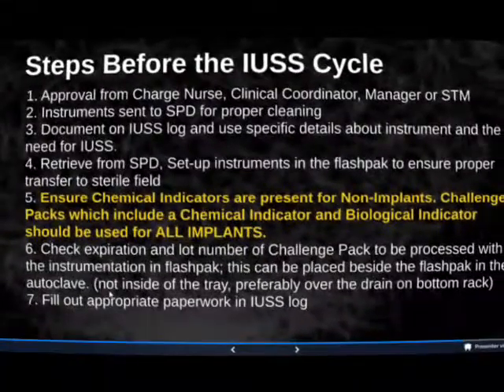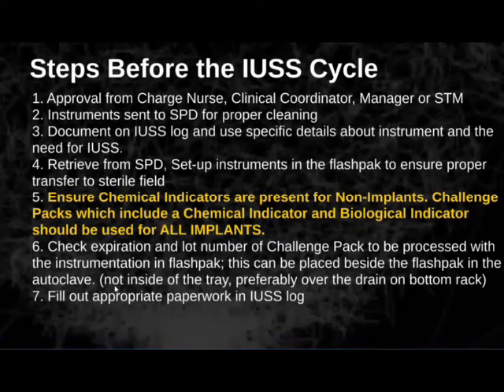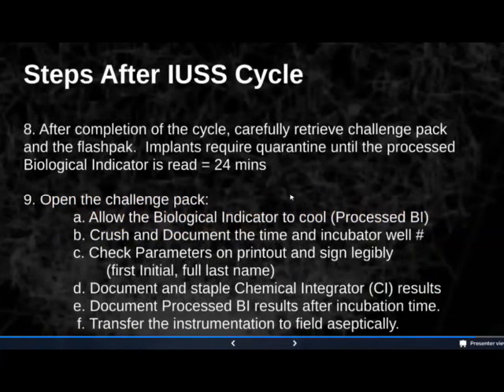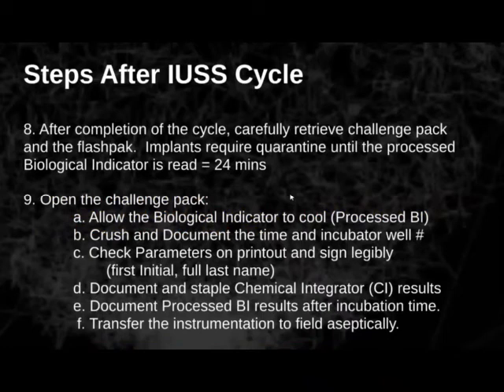All right, so once again, don't put it inside of the tray, preferably over the drain or on the bottom rack. It can be right inside of the autoclave, just beside the flash pack. So again, fill out the appropriate paperwork for the IUSS log, and then you can start your cycle. So after completion of the actual cycle, carefully retrieve the challenge pack and the flash pack.